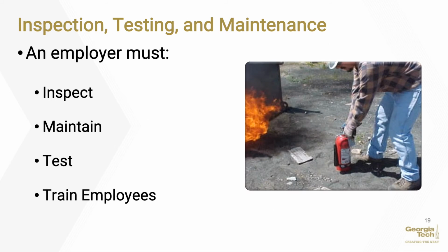An employer must inspect, maintain, and test all portable fire extinguishers in the workplace. Visually inspect portable extinguishers or hoses monthly. Perform an annual maintenance check on portable fire extinguishers. Stored pressure extinguishers do not require an internal examination.